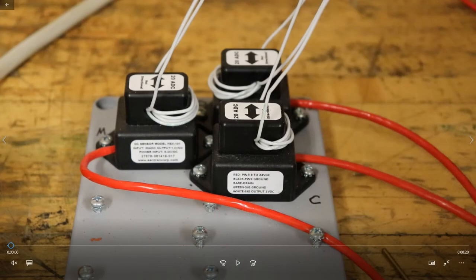As I mentioned earlier, the cable carrying the DC current needs to pass through the orifice of the sensor. The sensors are bidirectional, meaning the cable can be passed in any direction through the orifice. Also, if the current passing through the cable is much less than 20 amperes, it is advisable to make multiple loops through the orifice. This increases the accuracy of measurement.